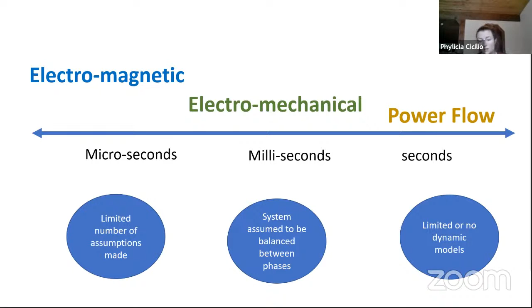Electromechanical simulators that use positive sequence, transforming the three phases into sequence components, are called positive sequence simulators. Those only produce accurate results when it can be assumed that the system is balanced, meaning that all three phases, A, B, and C, are carrying approximately the same amount and type of power. Electromagnetic simulators do not assume phase balance and are able to capture harmonics associated with the high frequency switching elements of the inverters. The detailed models of these devices, here we'll talk about inverter-based resource models specifically, also correspond to this timescale and these different simulators.